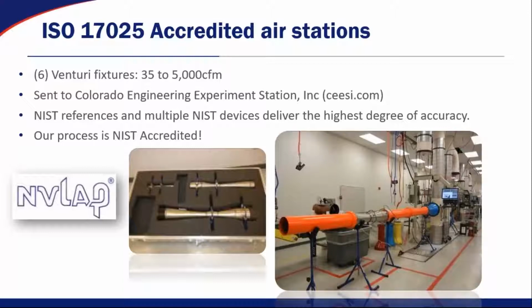So there's a fixed Venturi tube that has a known flow at a given pressure, and we set those up on each one of our air stations to guarantee the air station's accuracy before we actually calibrate the airflow control valves. In addition to that, we also have a third-party certification called the NVLAP, or National Voluntary Lab Accreditation Program, certify our air stations to guarantee the accuracy of the Phoenix products. So when we build and ship our valves, you have peace of mind knowing that the products are going to be plus or minus 5% because it's third-party validated.